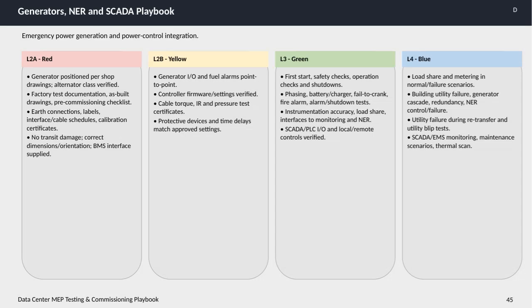On this slide, we're diving into the generators, NER and SCADA playbook, which is a critical part of emergency power generation and power control integration for data center MEP testing and commissioning. Starting with level 2A, marked in red, we ensure the generator is positioned exactly as per the shop drawings and the alternator class is verified. It's important to have all factory test documentation, as-built drawings, and the pre-commissioning checklist ready. We also confirm proper earth connections, labeling, interface and cable schedules, and calibration certificates.